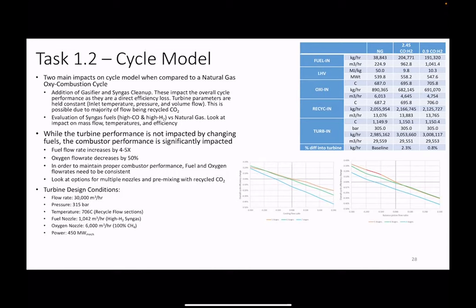This turbine is designed for a little lower temperature than the previous one, which was designed for 1200 C inlet - we're only looking at 1150 C inlet on this one. Between the different fuels, from natural gas to coal syngas, your fuel rate increases by almost 5 times, while oxygen flow rate decreases by 50%. So you have to develop a combustion system that can maintain velocities throughout these different fuels to maintain combustion performance, because very high or very low fuel velocities lead to off-design performance, incomplete combustion, and impacts on overall performance and temperature uniformity going into the turbine.